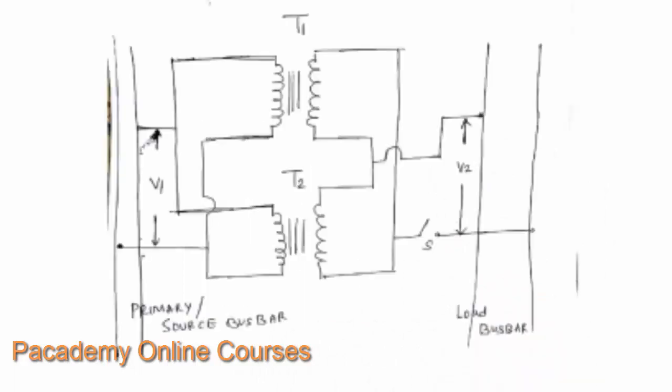In the connection diagram, there are two transformers T1 and T2. The primary windings of each transformer are connected to the source bus bar, with terminals of the same polarity taken together and connected to the positive terminal, while the other two are connected to the negative terminal of the supply. The secondary is sourced out similarly.